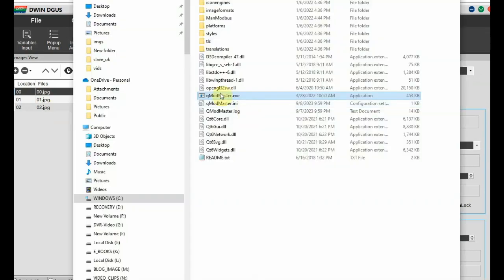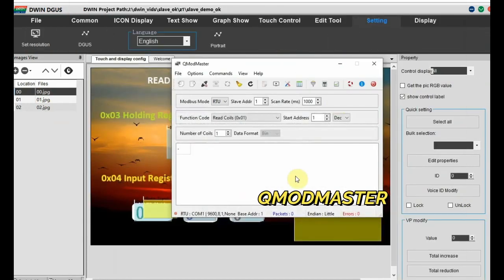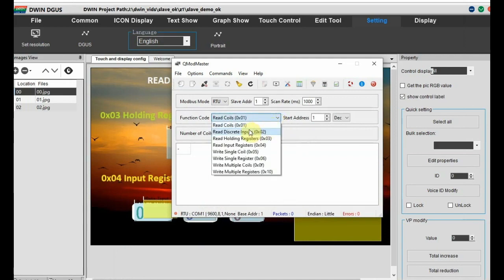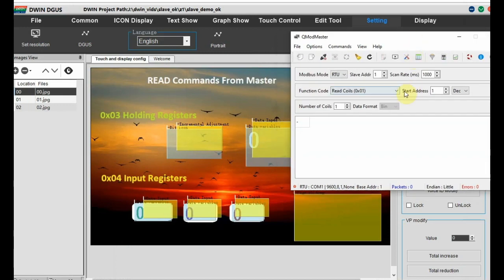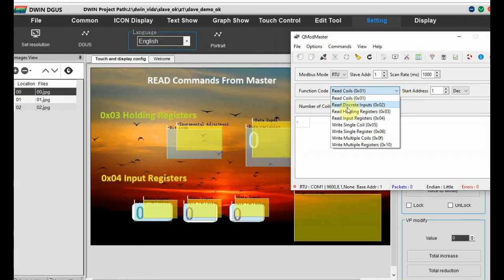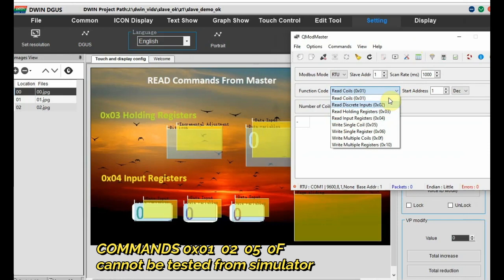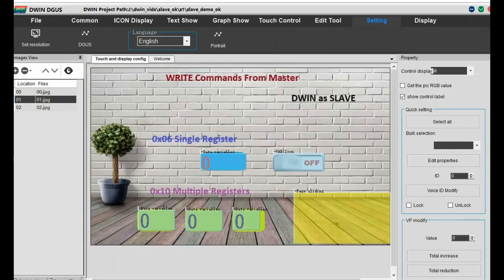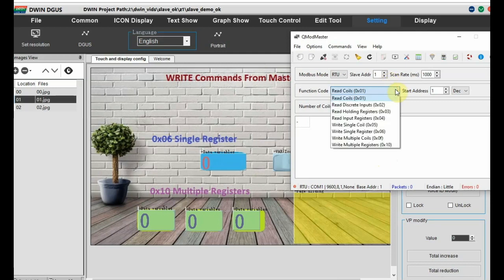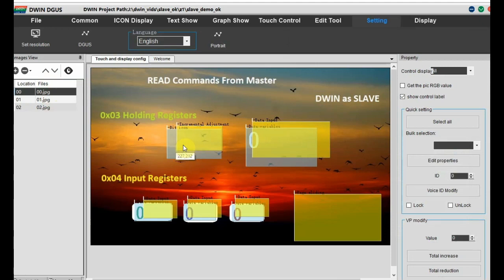For the master simulator software we will be using QMod Master, an open source simulator. Checking the function codes, there are four read commands and four write commands: read coil, read discrete inputs, read holding registers, and read input registers. We'll be testing read holding register 0x03 and read input registers 0x04. The other two commands can only be tested from a physical PLC. For write commands we'll be testing 0x06 for single register and 0x10 for multiple registers. Write single coil and multiple coils are not possible from this simulator - only from a PLC.